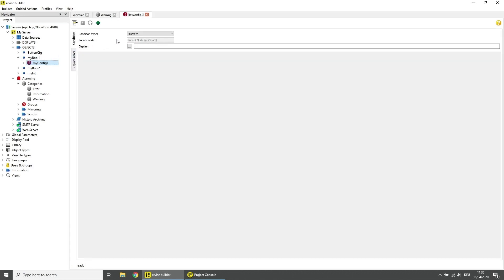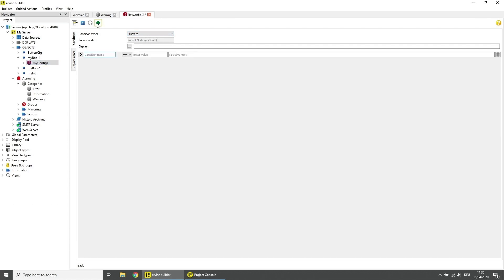The standard condition type for boolean data variables is Discrete. Click on the plus icon and click on it to add a new alarm condition. Choose the comparison operation and type in the value at which an alarm should be triggered. As the active text, enter a detailed description of the alarm.